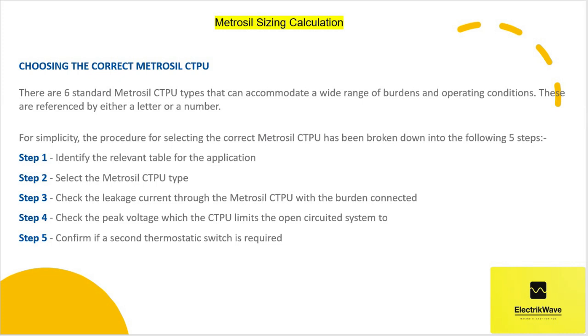Step 1. Identify the relevant table for the application. Step 2. Select the Metrosil CTPU type. Step 3. Check the leakage current through the Metrosil CTPU with the burden connected. Step 4. Check the peak voltage which the CTPU limits the open circuited system to. Step 5. Confirm if a second thermostatic switch is required.